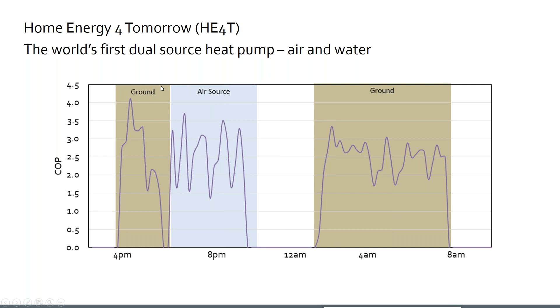And what it has shown is that you can basically get away with undersizing your ground source heat array by about half. So you have half the pipe depth if you're doing a borehole, half the ground source pipes. And because you're only switching over to air source at peak times, your seasonal efficiency isn't really affected all that much. So it's quite a remarkable way to add flexibility to a system, by having the ability to toggle between these two and really reduce the costs of a ground source while maintaining the performance of a ground source.